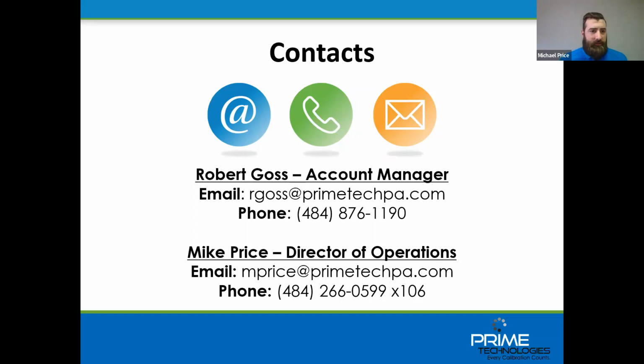Another question: can ProCal be used as a repository for scan certifications from vendors? Yes, that's absolutely something ProCal does, and many customers use it specifically for test standard certifications, but really any calibration done by an outside service provider or vendor. We have a manual pass-fail test type package which allows you to capture calibration results and attach scanned certifications, so you don't always have to key in the specific measurement results. You can just enter that the calibration was performed and scan in the actual certificate as an electronic copy, storing it in ProCal.